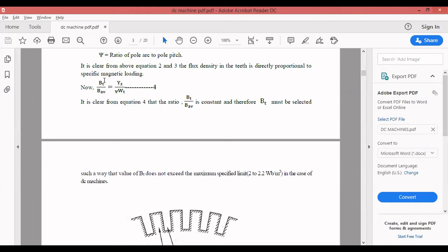For small machines, you have to go for a low value of specific magnetic loading. When a higher value of average flux density is selected, the MMF required by the iron part of the machine will be high, which results in large iron losses, increased copper loss, and increased cost. Magnetic flux density in the tooth should be selected within 2 to 2.2 Wb/m² such that the condition B_t / B_av remains constant.